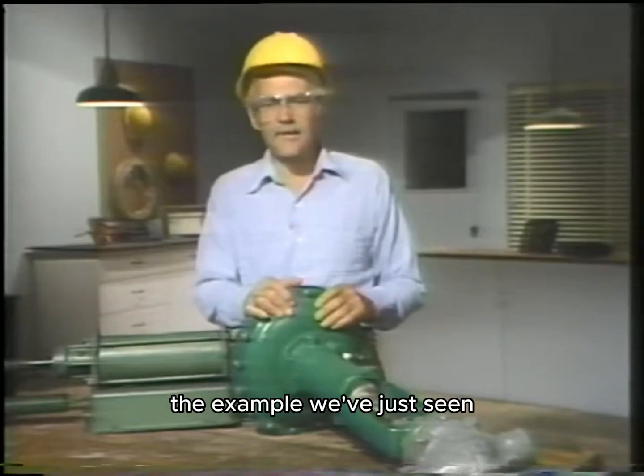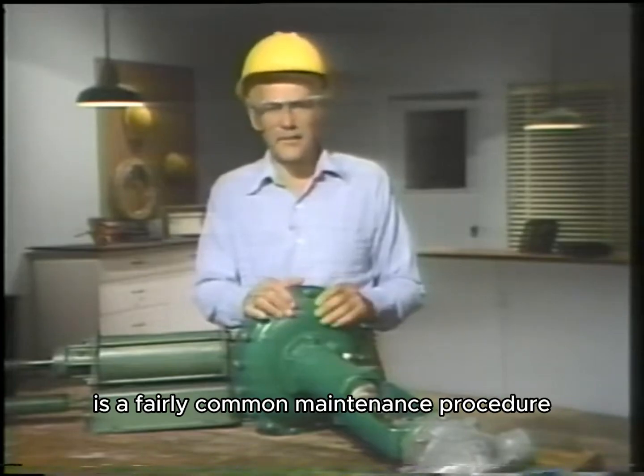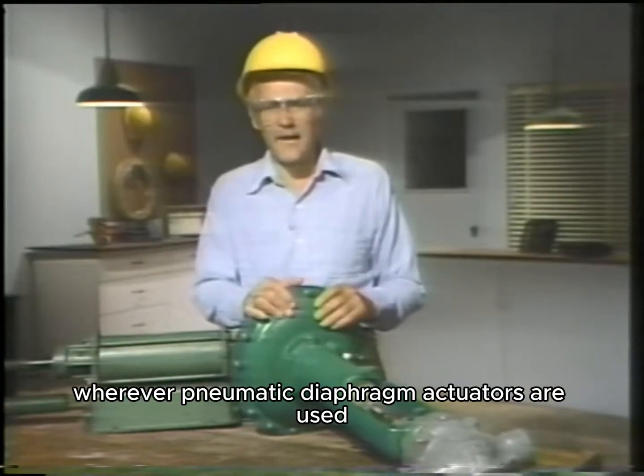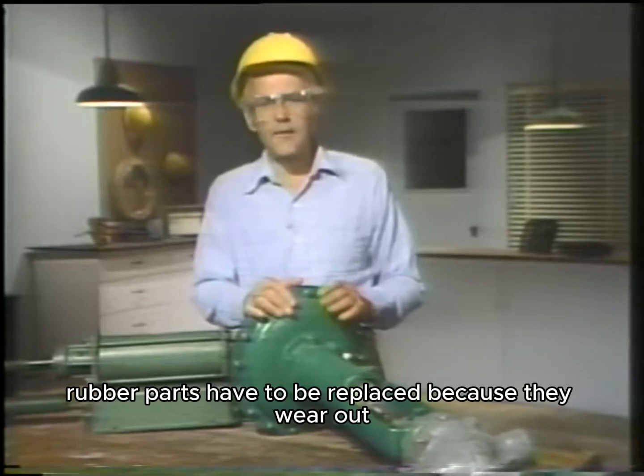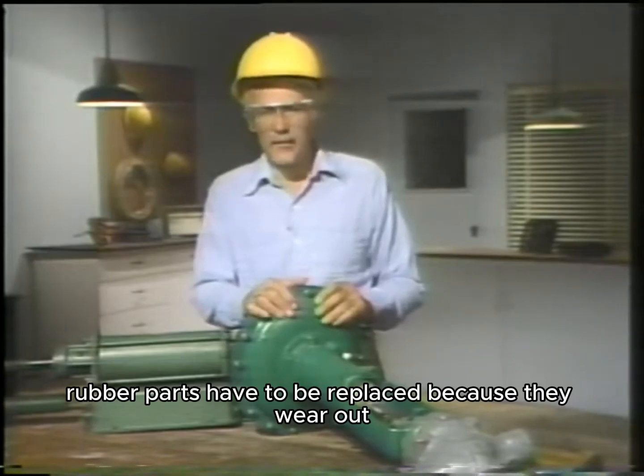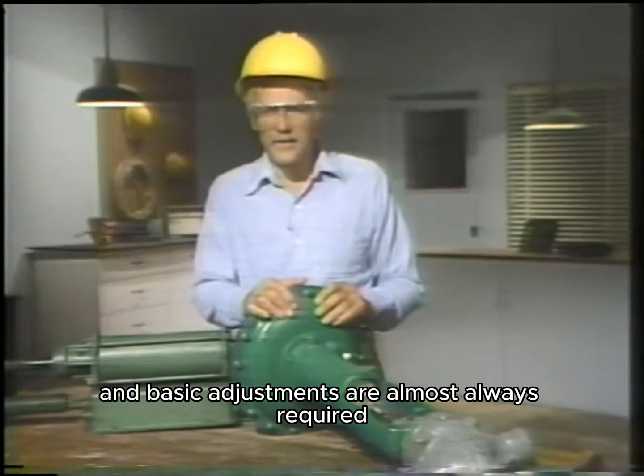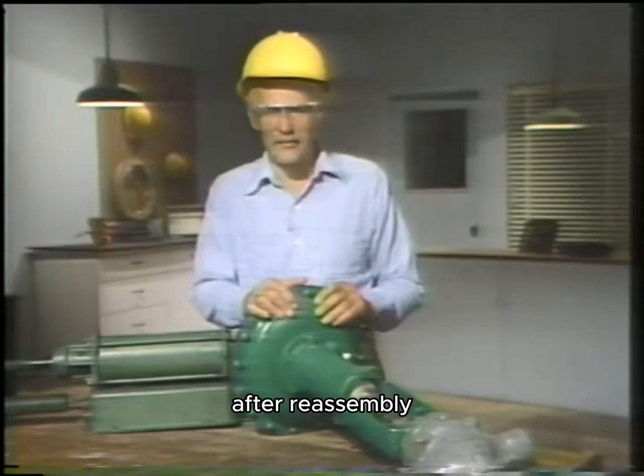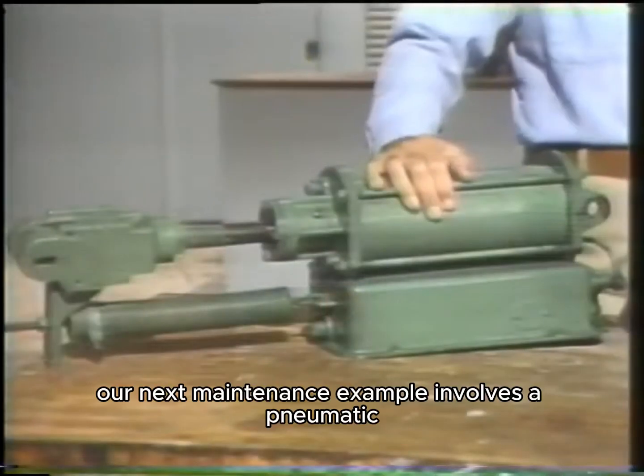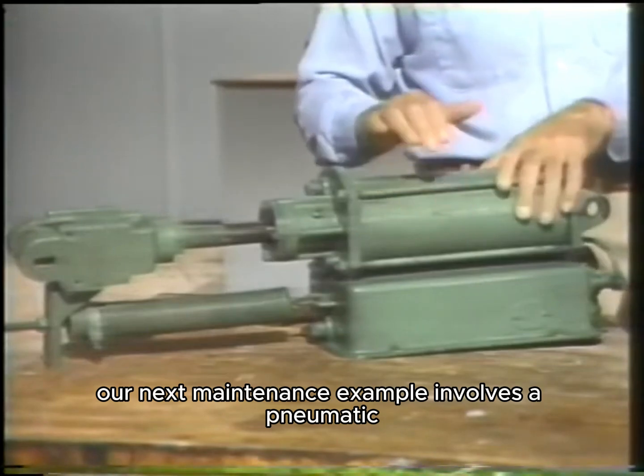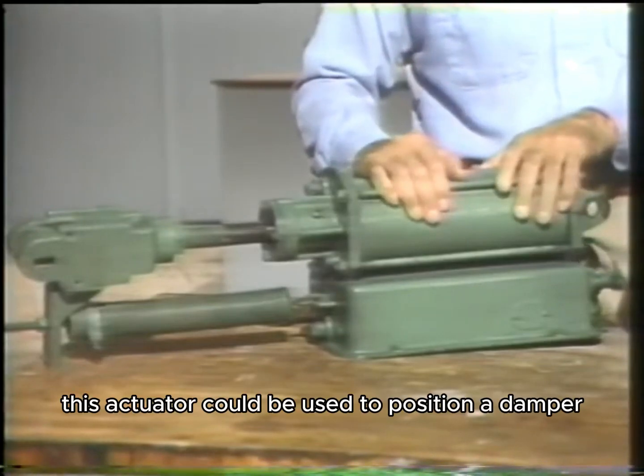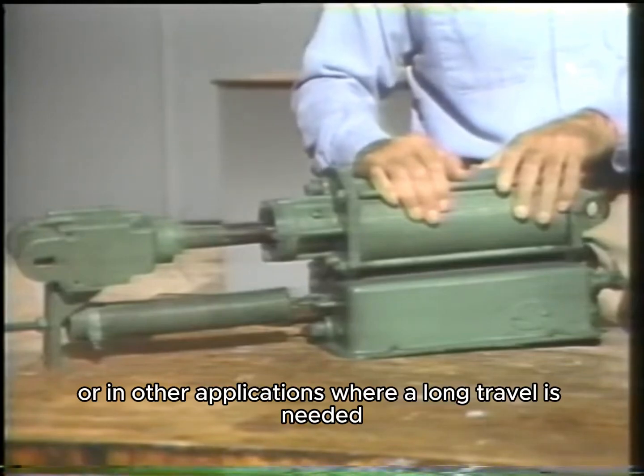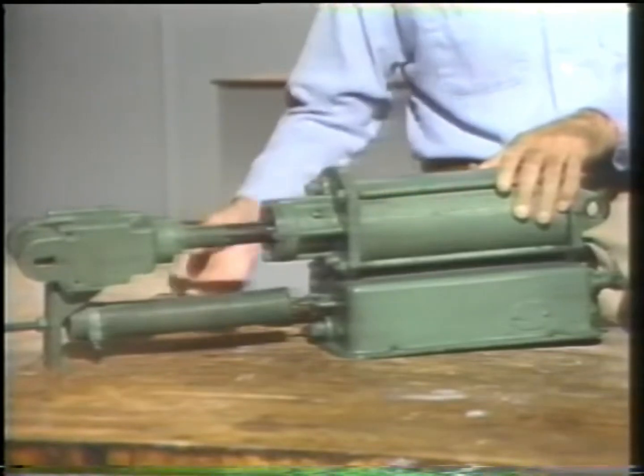The example we've just seen is a fairly common maintenance procedure wherever pneumatic diaphragm actuators are used. Rubber parts have to be replaced because they wear out, and basic adjustments are almost always required after reassembly. Our next maintenance example involves a pneumatic piston actuator. This actuator could be used to position a damper or in other applications where a long travel is needed.